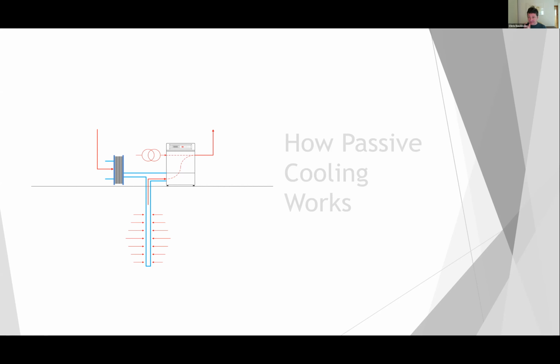Now, the advantage of this is that we don't have the compressor energy in the cooling side of things. We're simply running some pumps. So it can be a significantly more efficient way of cooling, provided the temperature regime in this ground loop is correct for passive cooling. And what that generally means is a significantly heating dominated building. So that ground loop's going to get cold and it's going to stay cold throughout its life. But as I say, a very effective way of cooling with very low energy input.